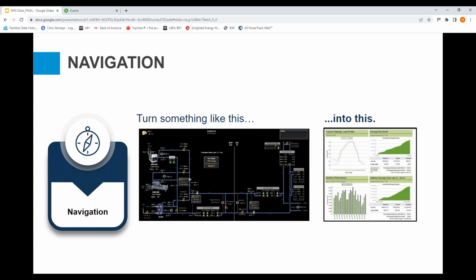The screen on the left is a building management system showing a chilled water plant, and the one on the right is an energy management system, with obviously a lot more charts and graphs. If you recall from day one, I showed you a heat map where we could look at all the VAV boxes in a building on one graph, and click directly to the one that's behaving badly. The alternate would be going through the BMS and clicking through each VAV box screen until you found the one behaving badly, which could take a long time if you had hundreds of zones in your building.